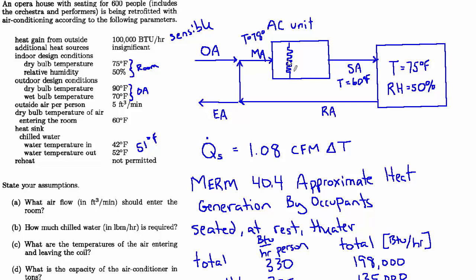it's likely that a significant percentage of it is being bypassed around the coil. So you could draw that kind of like this up and around and then coming in here and skipping past the coil. It's not getting cooled at all. No sensible cooling, no latent cooling, nothing.